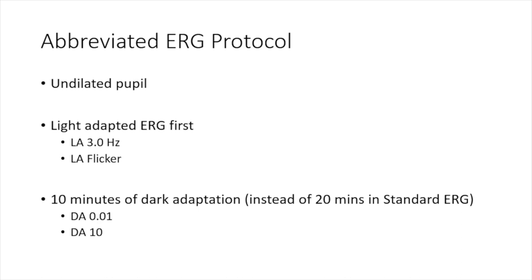The abbreviated ERG protocol was introduced in the 2021 updated ISCEV guidelines — it is newer and not yet widely practiced. It has certain advantages: it saves time and can be done in an undilated pupil. In a full field ERG, full pupillary dilatation is required. In an undilated state, the amount of retina exposed is less, so you will get reduced amplitude ERGs even in a normal individual — this is expected and normal for this protocol.